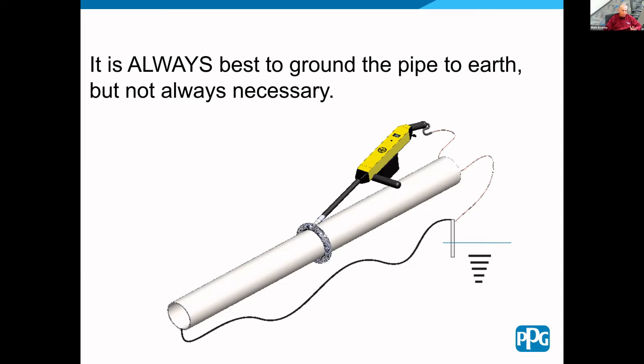If you can practice good earth grounding, it eliminates a lot of headache down the path. In the case of concrete, if we can't get a good ground to the rebar in the structure, or can't get a good earth ground outside of a buried structure such as a wastewater treatment plant, then we can always run a capacitance ground. The way we do that is take a 6-foot length of 3-foot wide, quarter-inch chicken wire, lay it on the bottom, put the ground wire on top of that, and then put wet bags of sand on top of the grounding mat. It works very, very well.